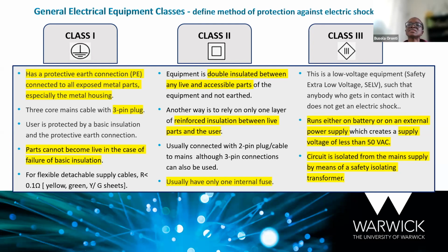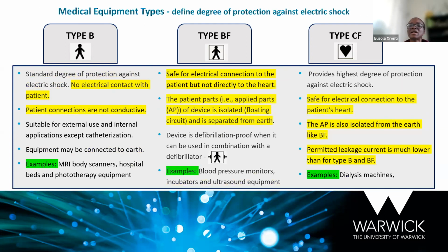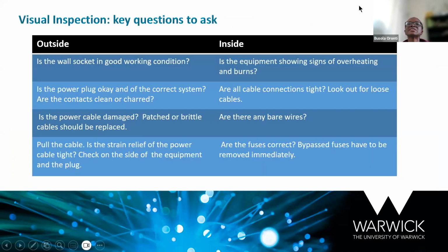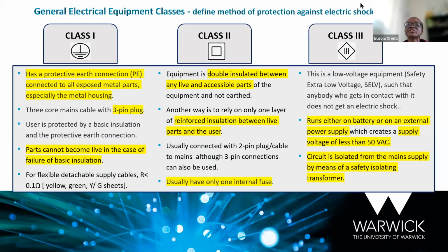And then for the class 3 device, how they do this is to isolate the circuit from the main supply by means of a safety isolating transformer. So generally, this is not just about medical devices. For all devices, these are the classes that we have. And what that says is the method of protecting people from electric shock. So it defines the method of protecting against electric shock.